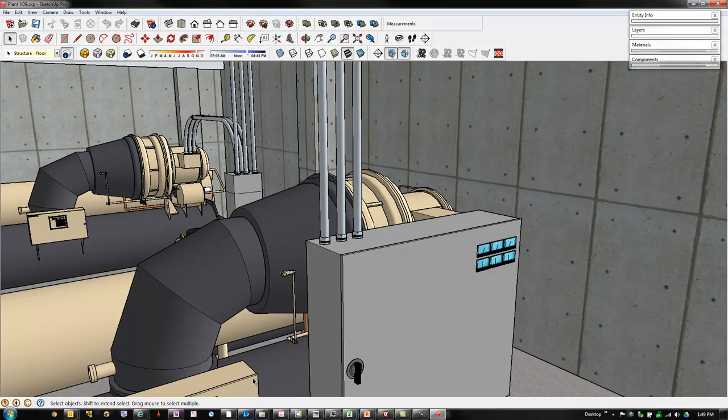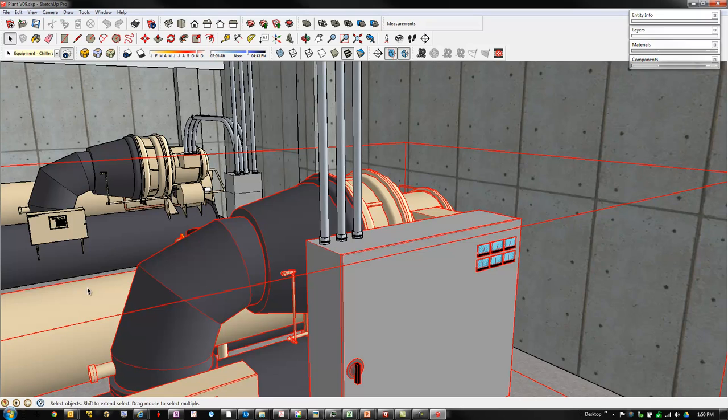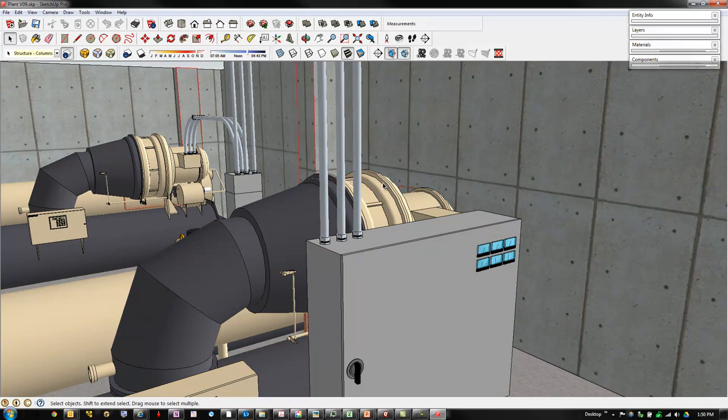and the refrigerant has to flow from the evaporator to the compressor, and so this is probably the suction elbow. The refrigerant's probably being drawn out of the evaporator into the compressor, into the impeller. The fact that there's two bumps probably tells you it's a two-stage machine. There's two impellers in there.